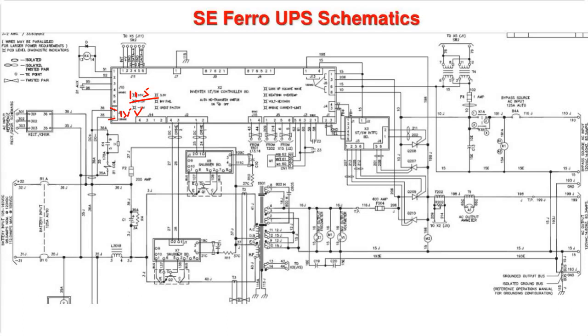So what it does is it sends a signal out to the K4 relay. You can see it up the top here. We energize K4, that closes this contact here. If you look, this is the positive DC, and this here is the negative, and the coil for the battery input breaker is connected in series with that contact. So when K4 energizes, the B1 coil energizes, and that trips this breaker and disconnects the battery from the system.